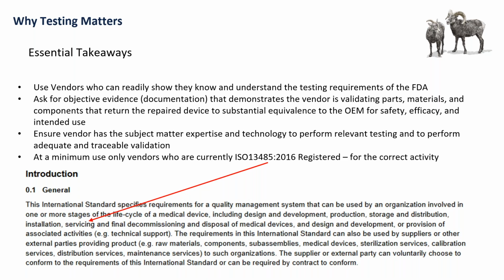So this guy got in a little bit of heat because he didn't check. I don't know what it is. But here's what I do know: if you don't know, find out. Don't just check these boxes, because that does go to the FDA, and if it says no, it wasn't replaced or repaired by a third party, they go after the OEM, right?